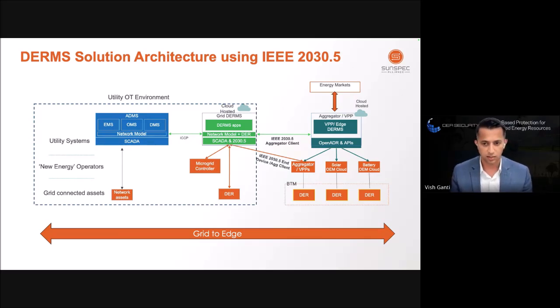It communicates either directly to the sites, which are behind the meter, or can send that information to an aggregator so the aggregator cascades it down to the DER. They could use other formats like OpenADR or other protocols, but the de facto protocol that the grid DERMS supports for this use case is IEEE 2030.5, which is tested and provided by SunSpec Alliance.